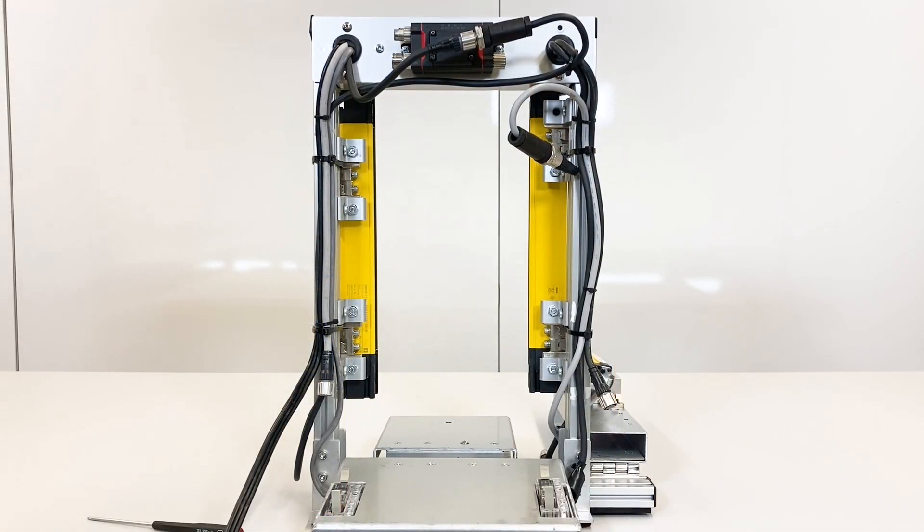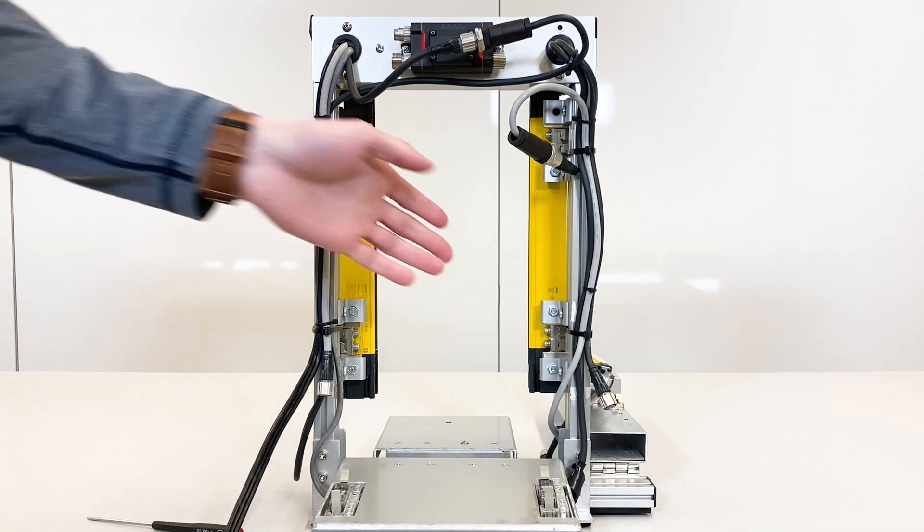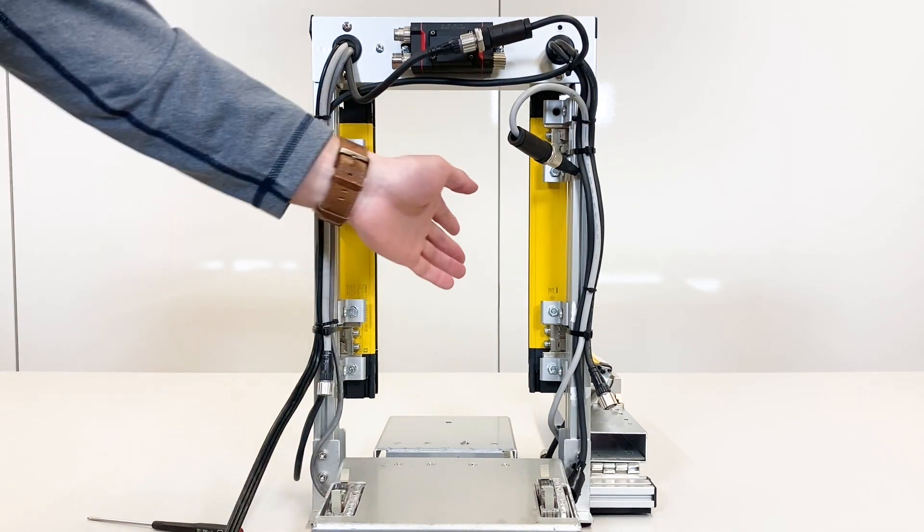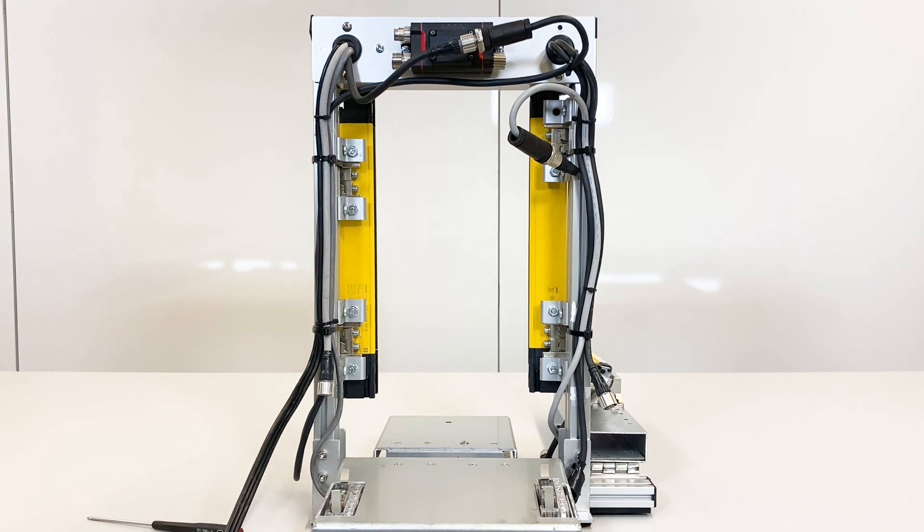So now your light curtain is programmed with EDM. And to confirm that everything is working properly, you can just pass your hand through the light curtain to make sure it is signaling output, which it is.